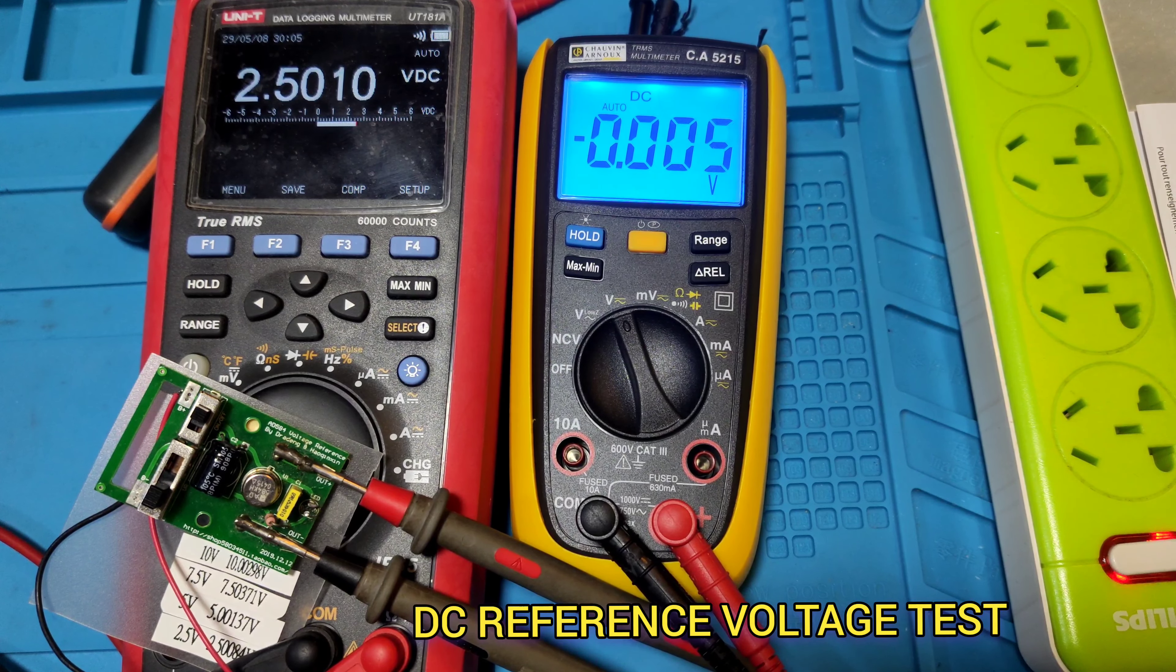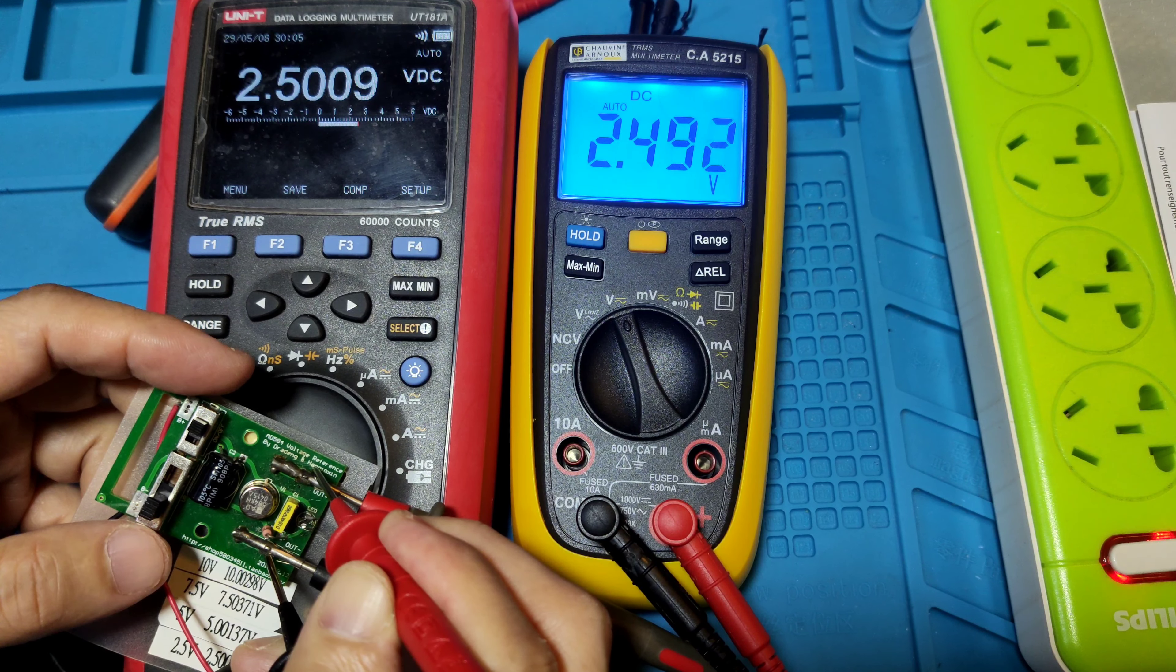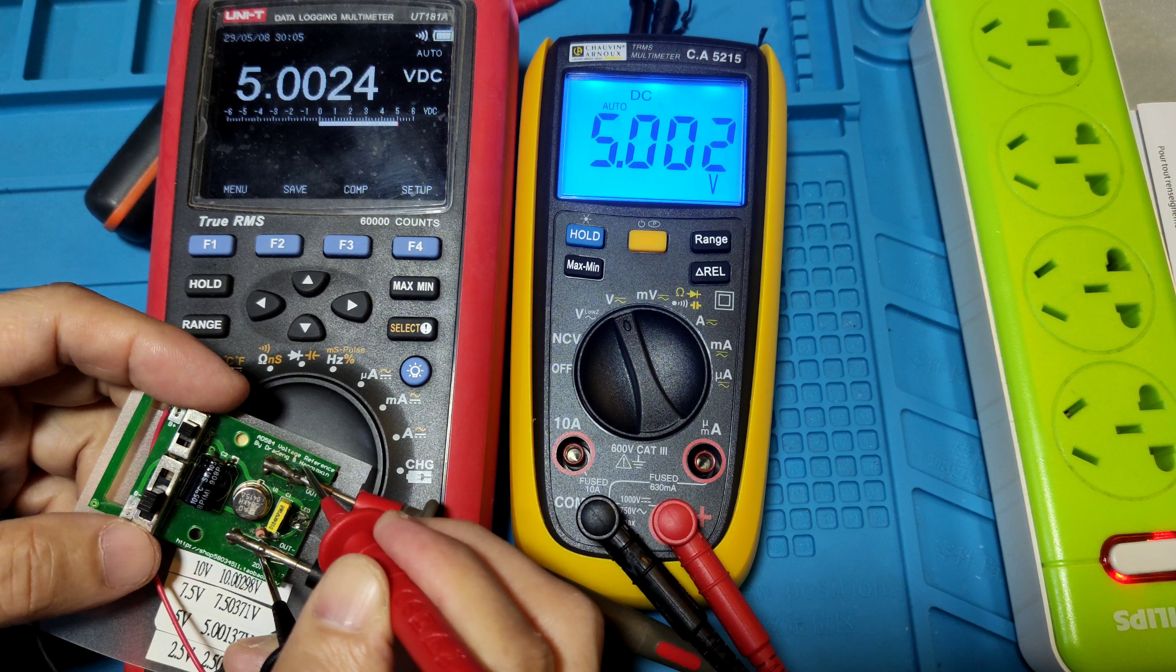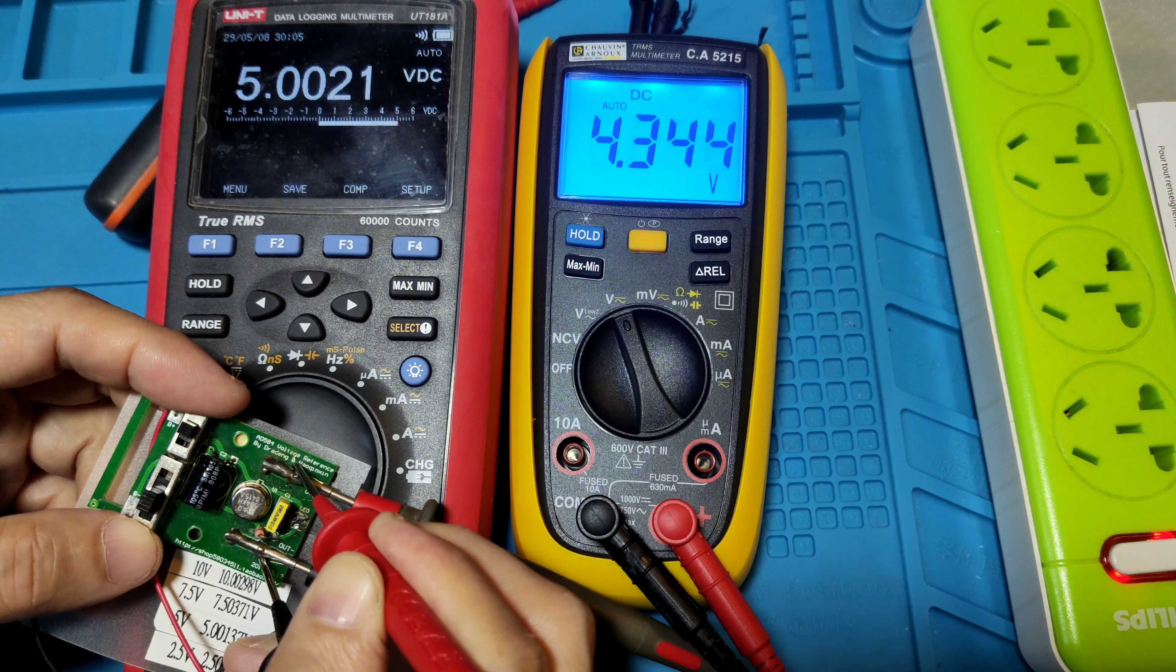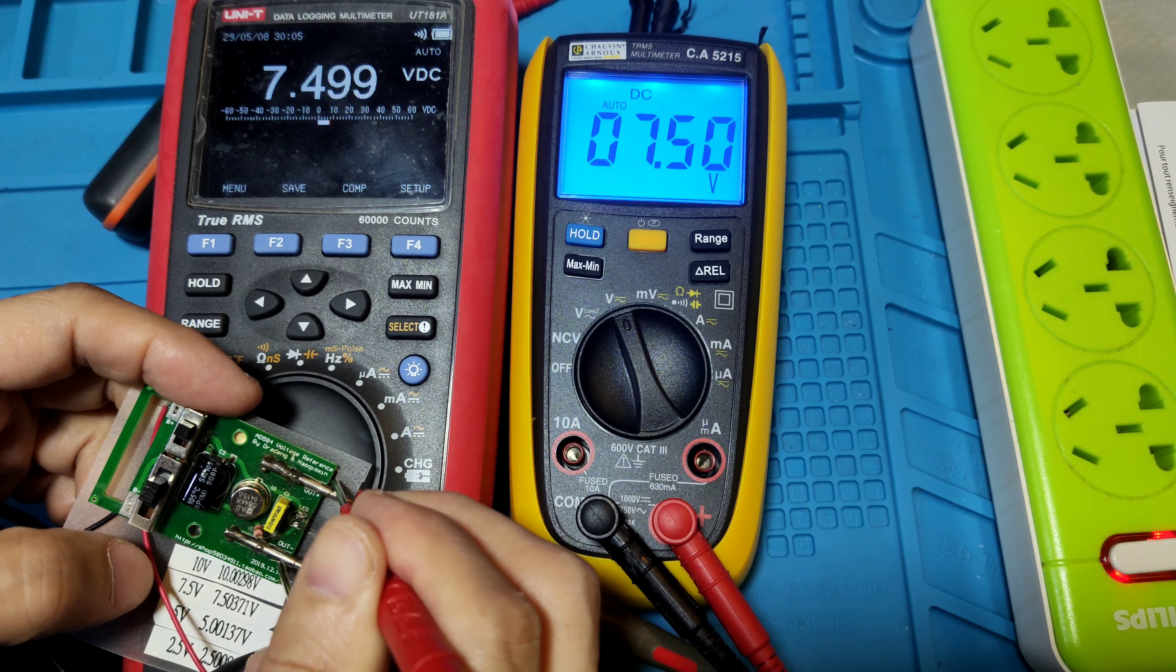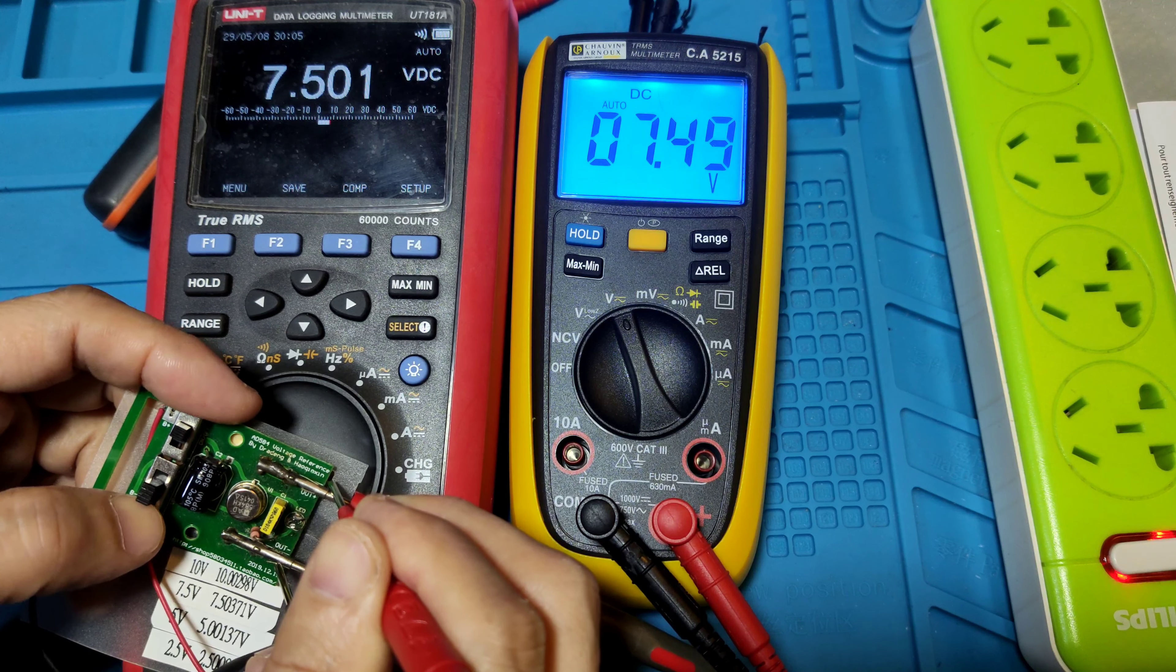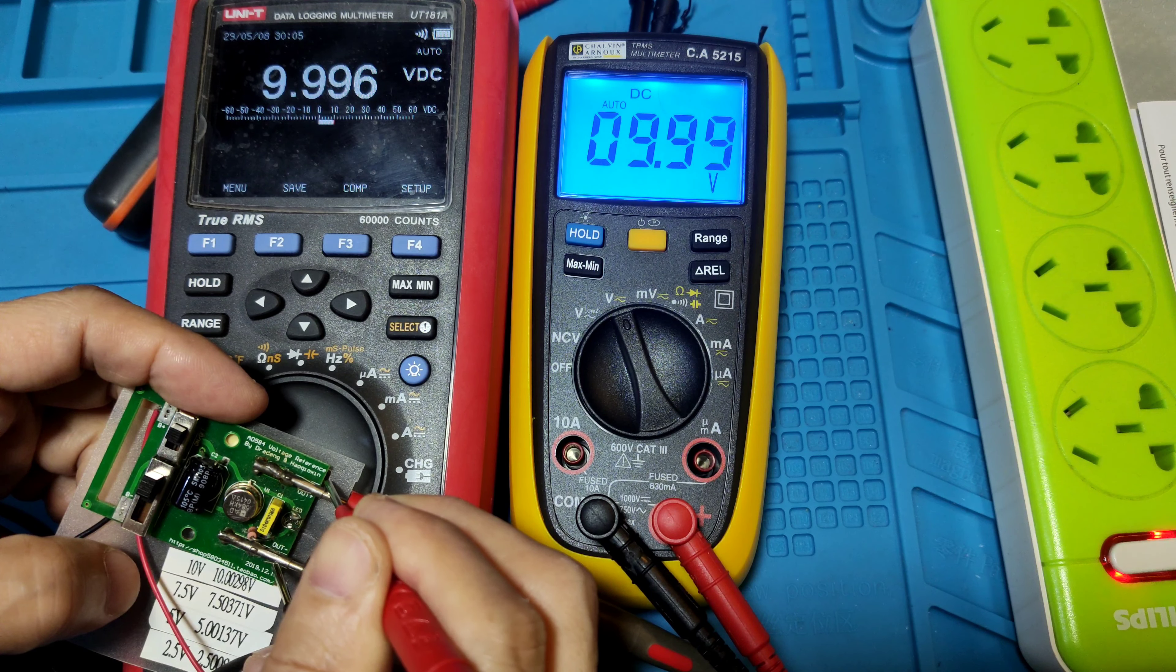Let's test the meter with DC voltage test. 2.5 volts, it shows 2.502 volts. 5.0 volts, it shows 5.003 volts. 7.5 volts, it shows 7.49 volts - near the reading. 10 volts, it shows 9.99 volts.